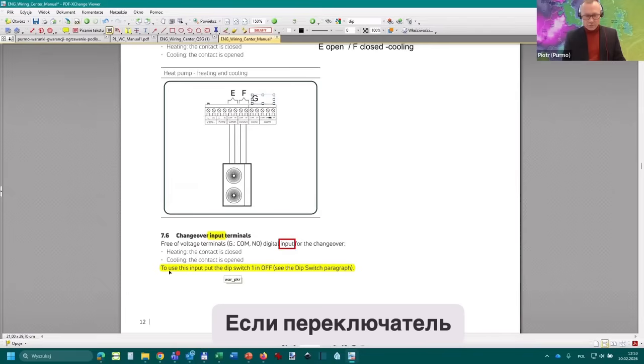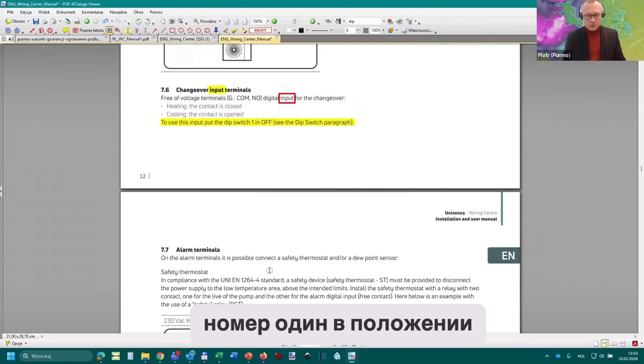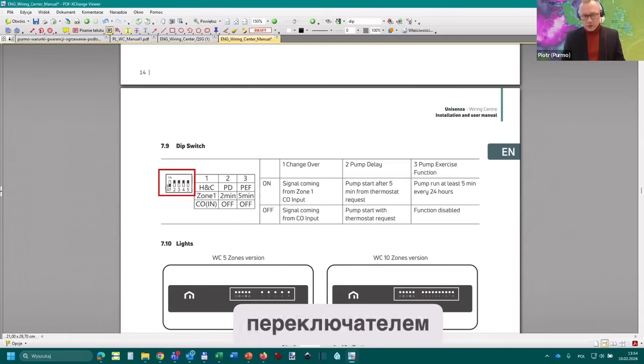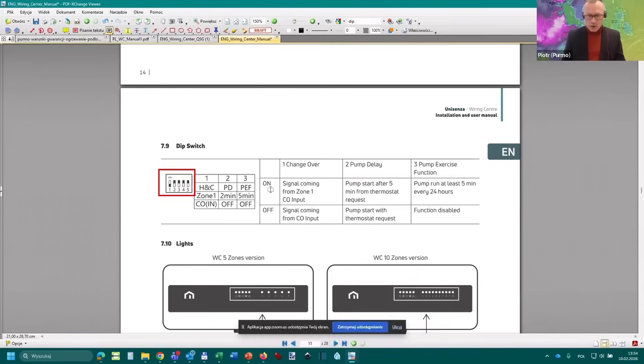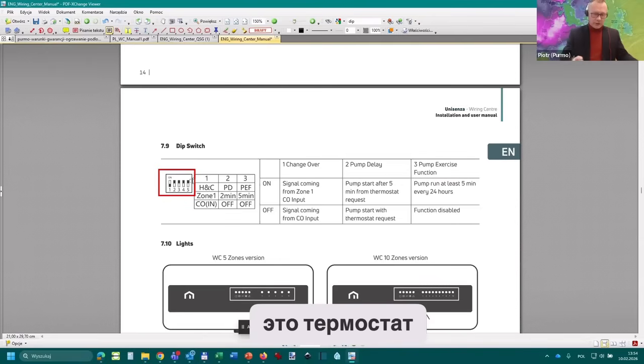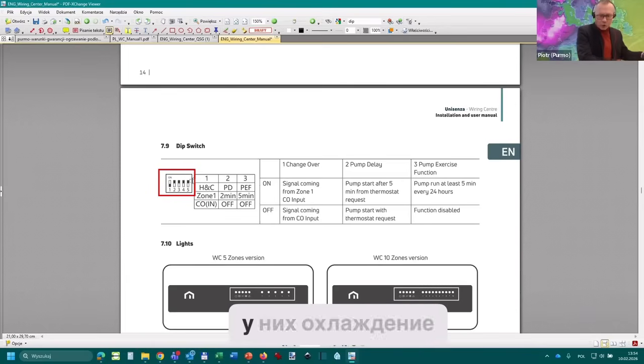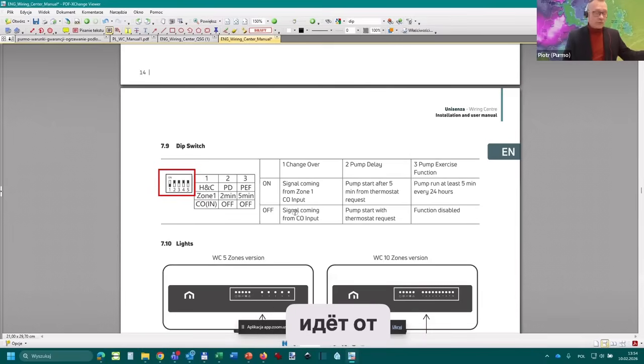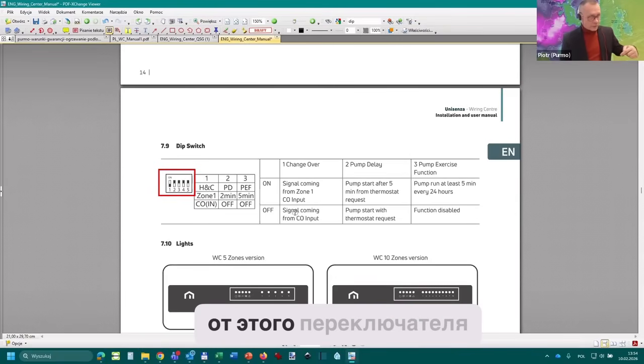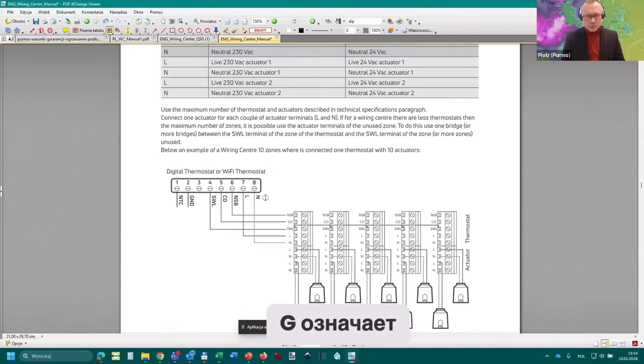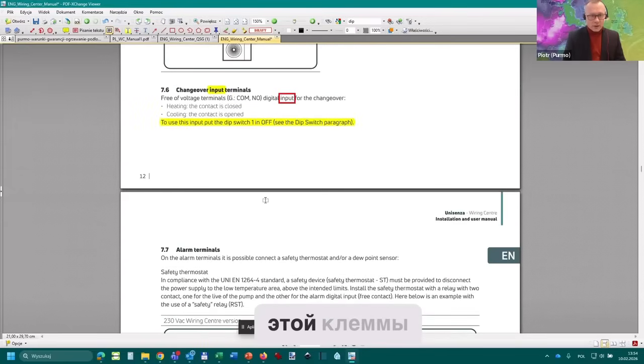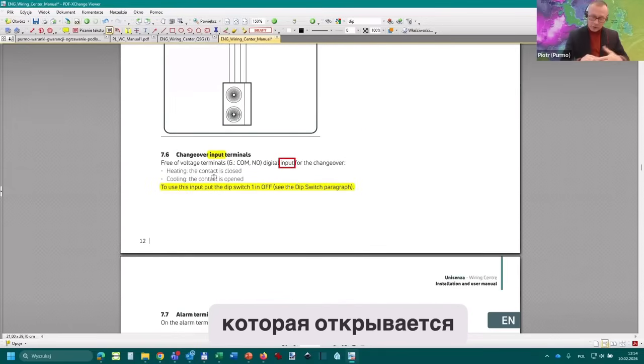If the DIP switch number 1 is in the off position, it means by this switch we decide if the master is a thermostat. This is a factory setting, so the master is the thermostat. It means the thermostat rules the source and asks it for cooling. Then the signal is coming from this switch G, from this terminal, which is open or closed.